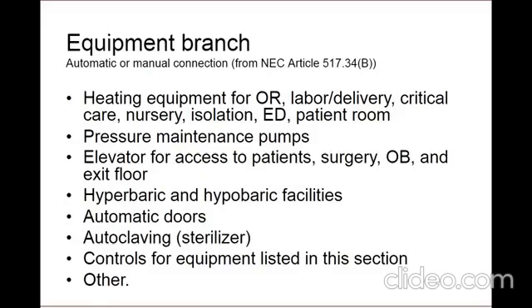Additional equipment includes pressure maintenance pumps such as jockey pumps for fire protection, at least one elevator that provides access to patient floors, surgery floors, OB, and the ground or exit discharge floor, hyperbaric and hypobaric facilities, automatic doors, autoclaving equipment or sterilizers, and controls for all the equipment listed here. And then again, just like the critical branch, there's nothing that limits you from putting additional equipment on this branch as long as it doesn't already belong on a different branch and is required for effective hospital operations. So this could be items such as chillers or additional air handler units or other things that you would want on emergency power.